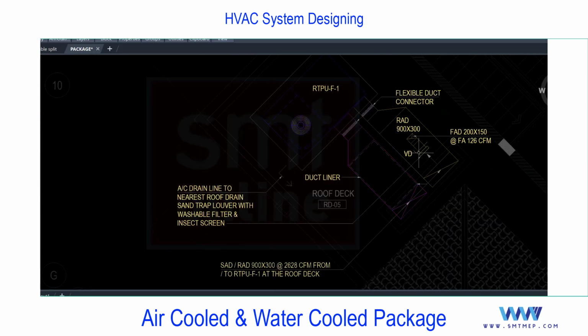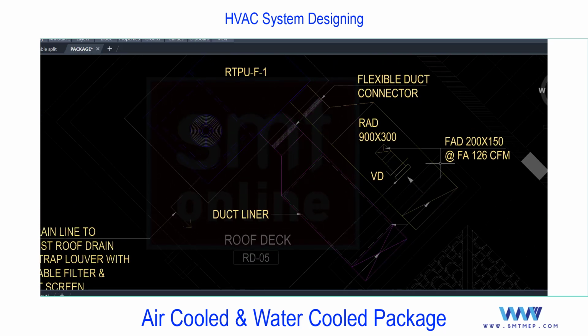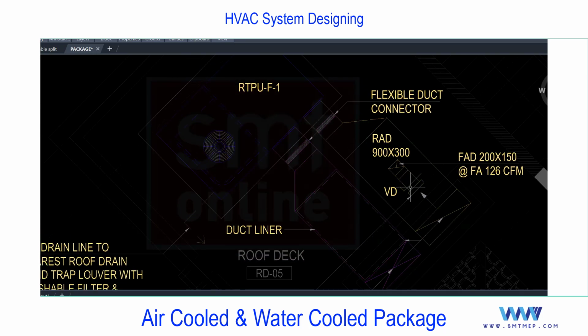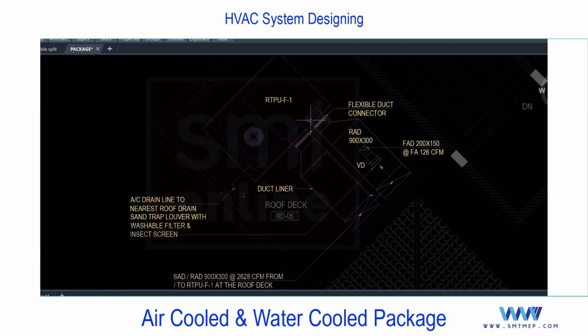to this floor. And now you can find the opening FAD, fresh air duct, you see, with the VCD. So we are connecting the fresh air duct with the VCD like a valve. So normally it's open so that the fresh air is introduced with the return air. So fresh air and return air mix and supply back to the rooftop package unit at the evaporator side only. The condenser side is totally separate from these ducts.